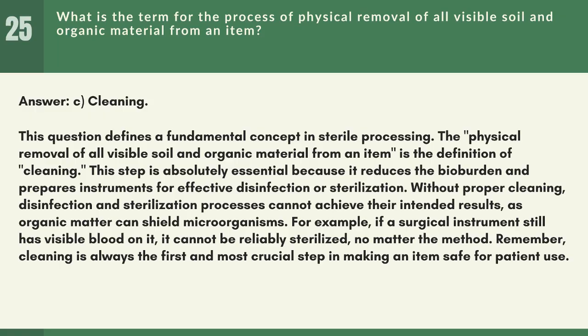Without proper cleaning, disinfection and sterilization processes cannot achieve their intended results, as organic matter can shield microorganisms. For example, if a surgical instrument still has visible blood on it, it cannot be reliably sterilized, no matter the method. Remember, cleaning is always the first and most crucial step in making an item safe for patient use.